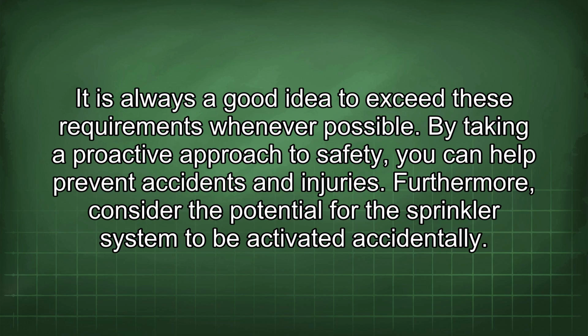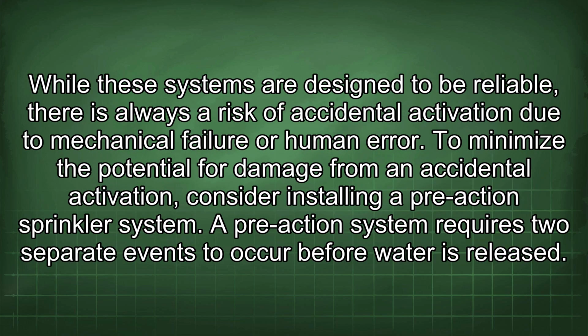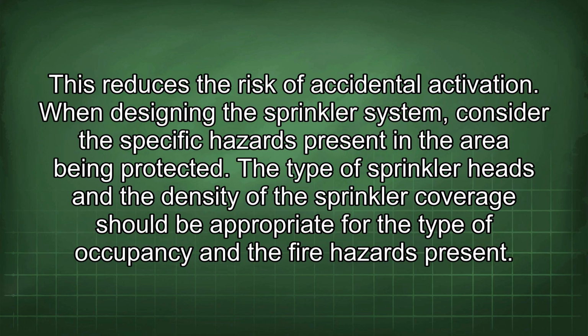Furthermore, consider the potential for the sprinkler system to be activated accidentally. While these systems are designed to be reliable, there is always a risk of accidental activation due to mechanical failure or human error. To minimize the potential for damage from an accidental activation, consider installing a pre-action sprinkler system. A pre-action system requires two separate events to occur before water is released. This reduces the risk of accidental activation.